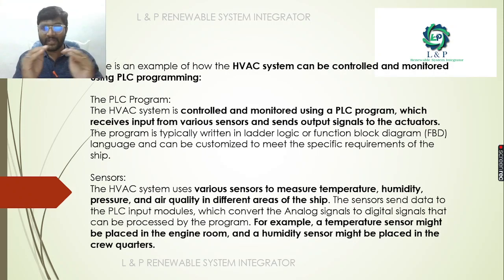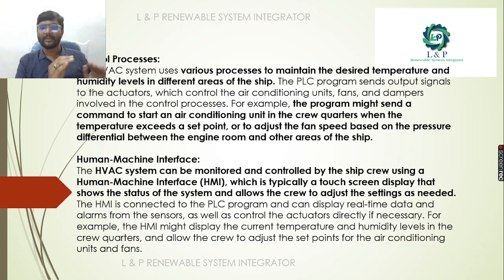So how does the program work? The first is that we need to control and monitor with the help of sensor inputs, and we are controlling the actuators. Mostly using sensors, we will try to measure temperature, humidity, pressure and air quality at different areas of the ship. Say for example, a temperature sensor might be placed in an engine room, and a humidity sensor might be placed in the crew quarters. Next, HVAC process. Most importantly, using the PLC program, using output signals, we command the actuators, air conditioning units, fans and dampers. Using PID loops, we control the entire process of this HVAC system.